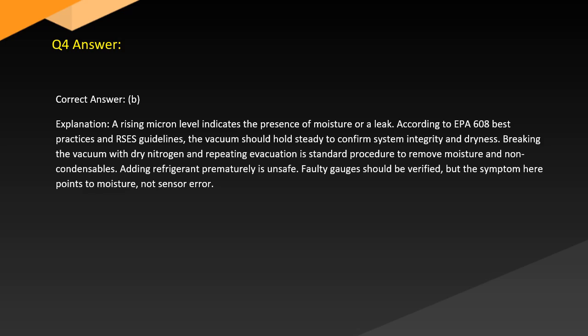Answer. Correct answer: B. Explanation. A rising micron level indicates the presence of moisture or a leak. According to EPA 608 best practices and RSES guidelines, the vacuum should hold steady to confirm system integrity and dryness. Breaking the vacuum with dry nitrogen and repeating evacuation is standard procedure to remove moisture and non-condensables. Adding refrigerant prematurely is unsafe. Faulty gauges should be verified, but the symptom here points to moisture, not sensor error.